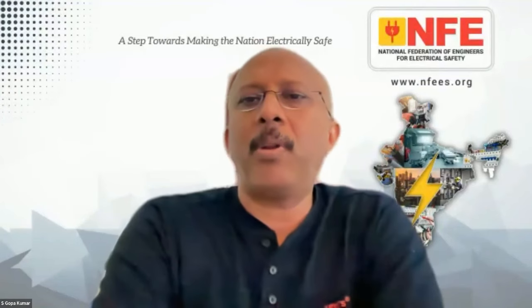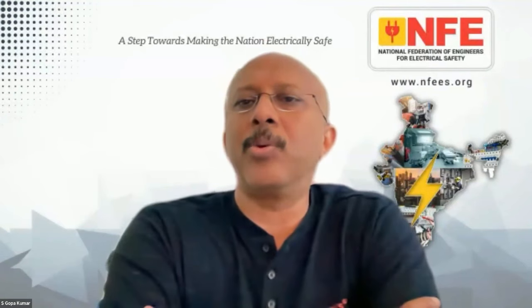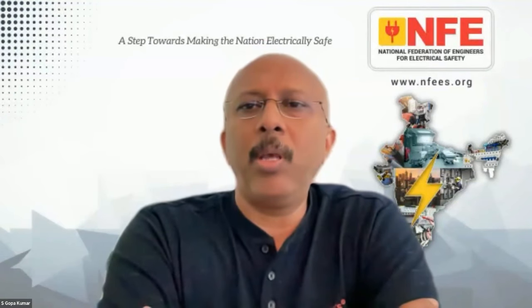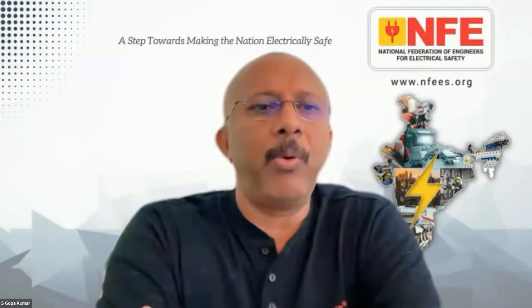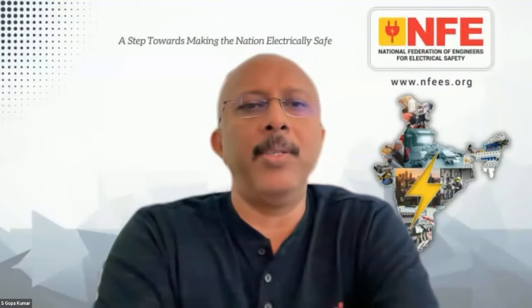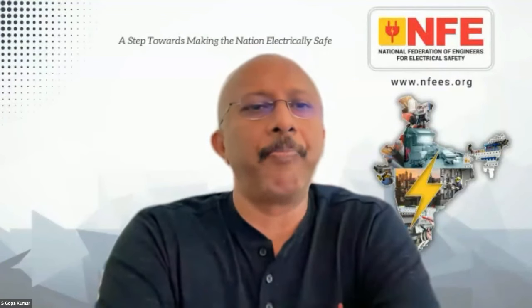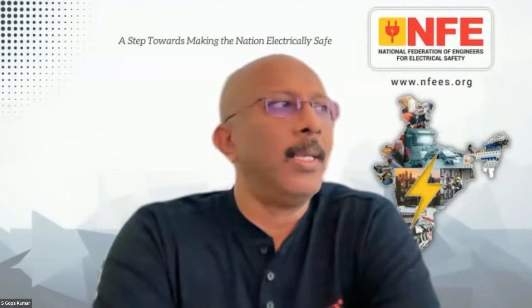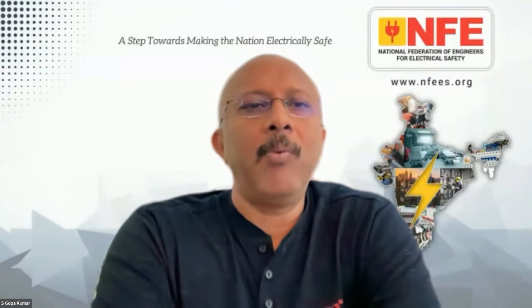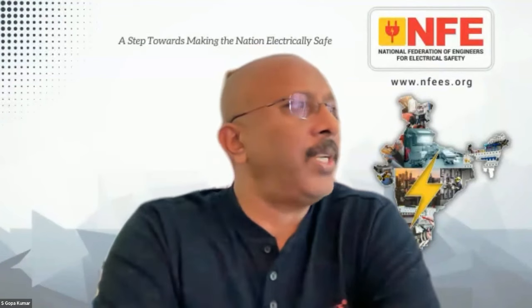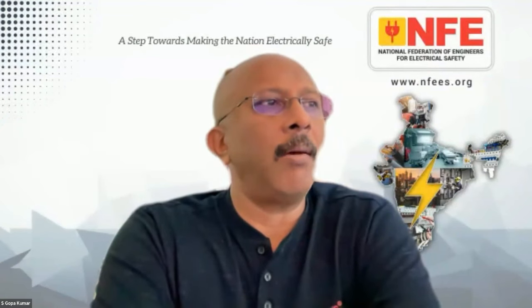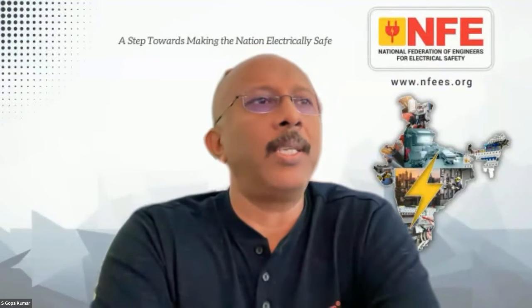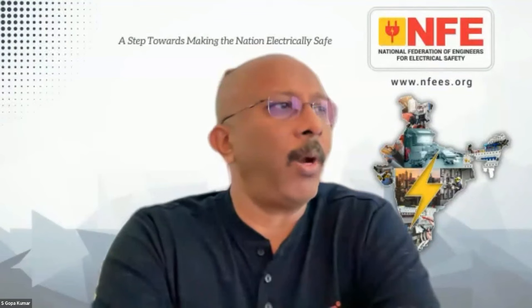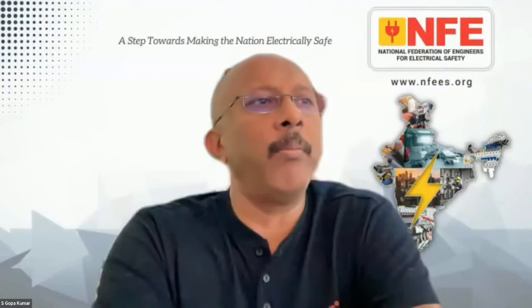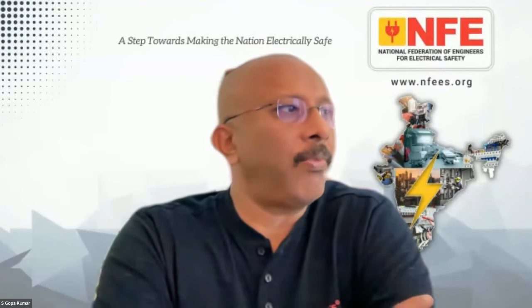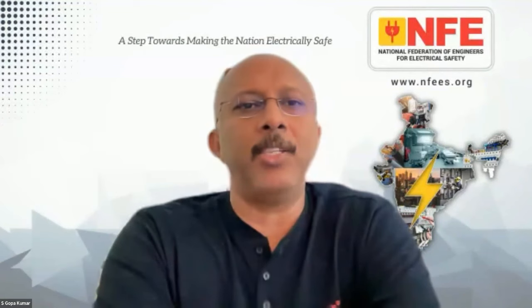There may be chances for mistakes also in this standard. For example, if you look at the IE rule or the CEA regulation 2010, regulation number 41, sub-regulation number 10, what it writes is, no person shall make a connection with the earth by the aid of, nor shall he keep in contact with any water mains not belonging to him, except with the consent of the owner thereof and the electrical inspector.